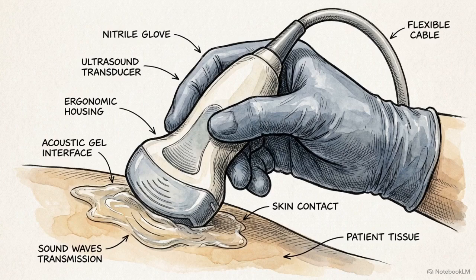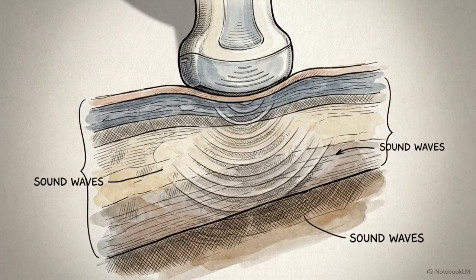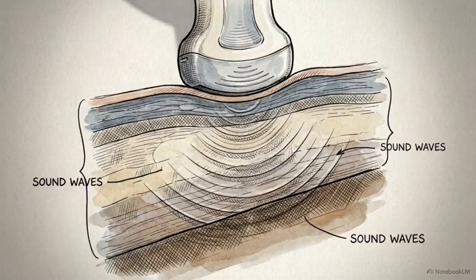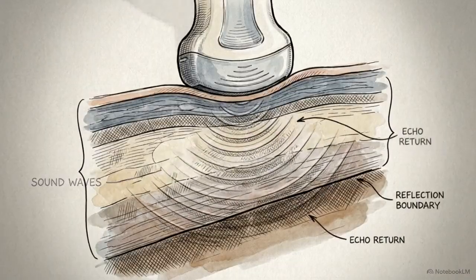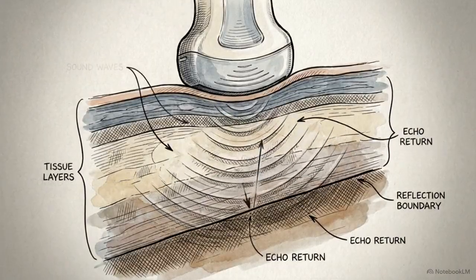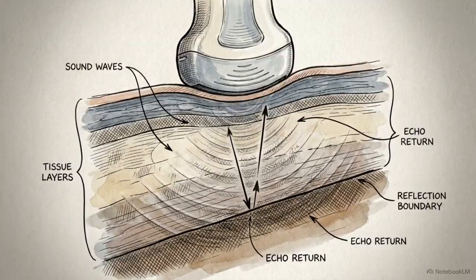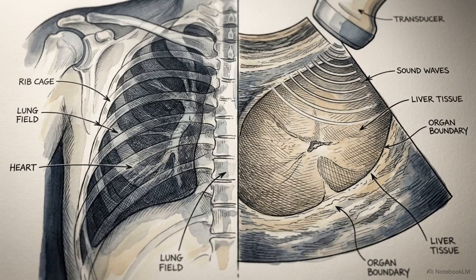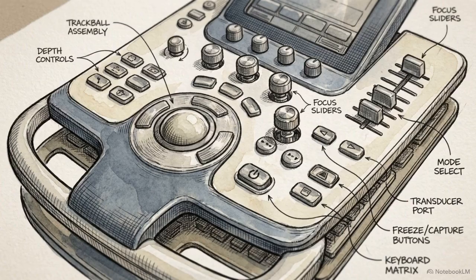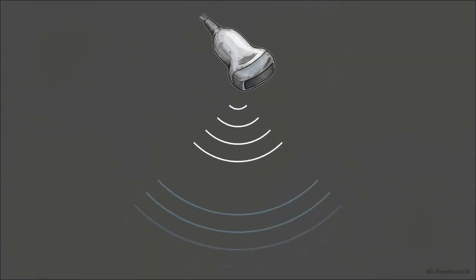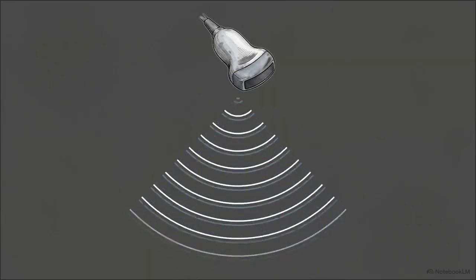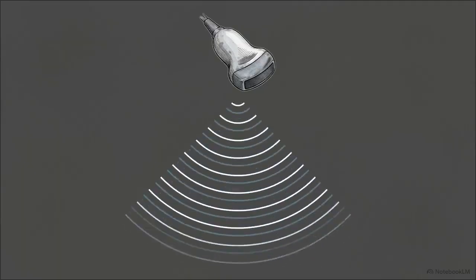When a clinical probe rests against the skin, it transfers energy directly into the human body. Every image produced is the result of a physical, mechanical, acoustic wave interacting with living tissue. Unlike a CT scan or an X-ray, ultrasound relies entirely on the absence of ionizing radiation. Instead, the machine functions as a highly calibrated transceiver. It must emit high-frequency physical vibrations and simultaneously record the returning echoes.